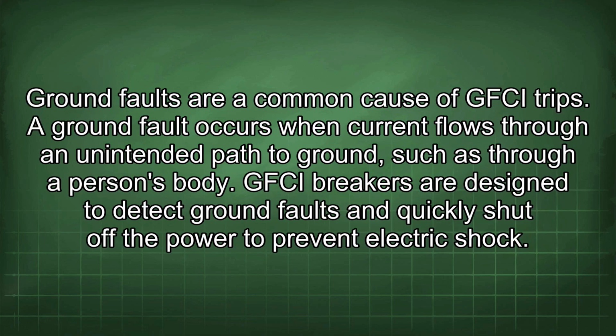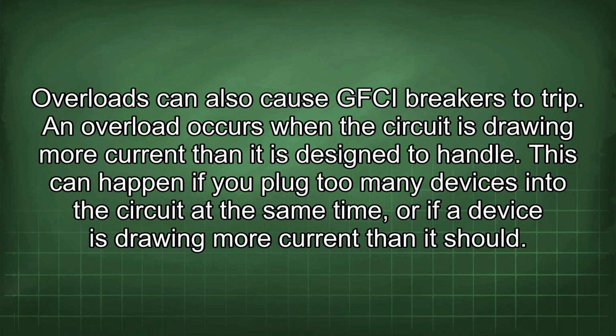Ground faults are a common cause of GFCI trips. A ground fault occurs when current flows through an unintended path to ground, such as through a person's body. GFCI breakers are designed to detect ground faults and quickly shut off the power to prevent electric shock. Overloads can also cause GFCI breakers to trip.